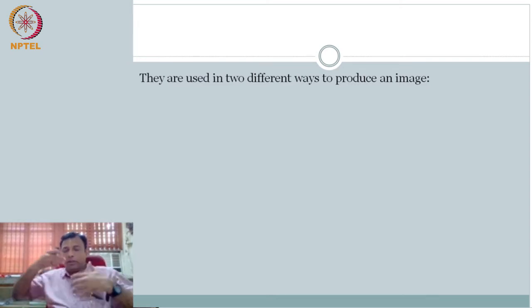So if I want only a particular location, right, to respond, what can I do? Okay, I put it in the magnet. I have everything aligned in the Z direction. Now I can also actually apply gradients, right? So each location has a different magnetic field. But instead what I will do is, I will try to apply the magnetic field, and then what do I need to do? I have to apply my RF excitation. What frequency will I apply RF excitation? I have to apply RF excitation at a particular frequency. Well, a particular Larmor frequency which I want to choose.